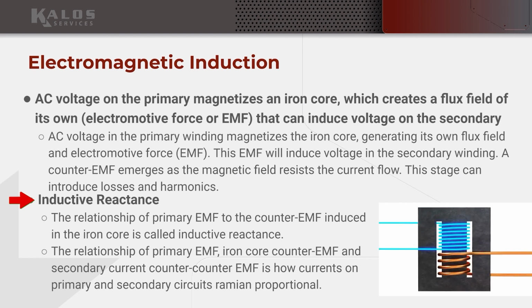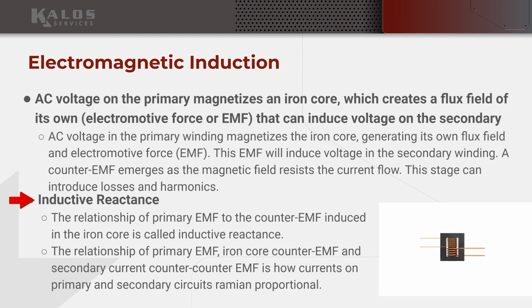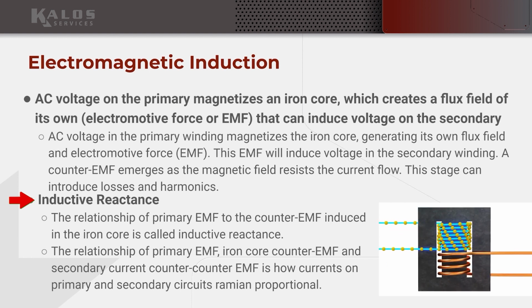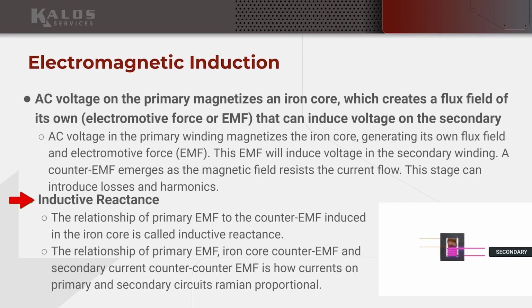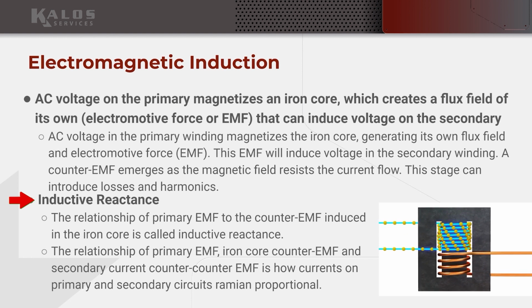If this were just a resistive load, like a light bulb, and you turned it on, you'd have a short circuit, you'd pull an immense amount of current, and the circuit breaker would blow. But this doesn't happen in inductive loads, such as transformers and motors. Resistance doesn't exist when it's at rest. It exists, in the case of motors, when there is movement, or in a transformer, when there is counter EMF produced by the magnetic core.